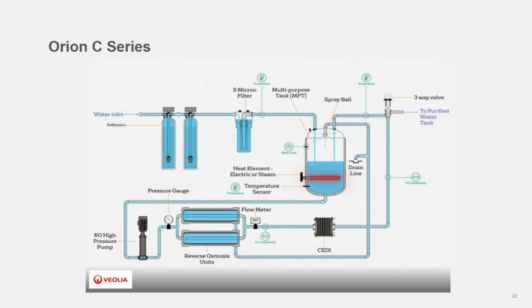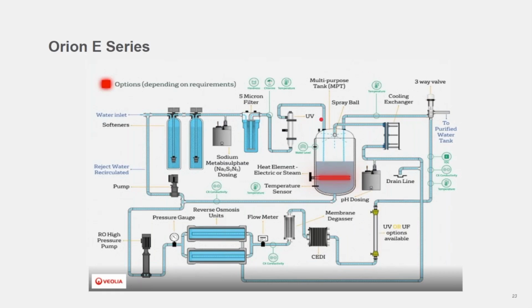It gets to all the parts of the system. As we say, with these sensors in place, you can map that hot water sanitization cycle, and we can do these cycles up to once a week, where traditionally chemical sanitization was possibly done maybe every 3, 6, or once a year. And you don't need any additional skids for chemical sanitizing. It's all done within the skid of the Orion unit.